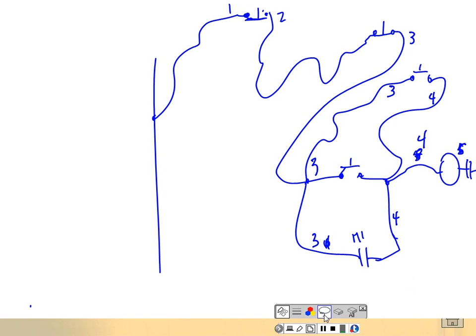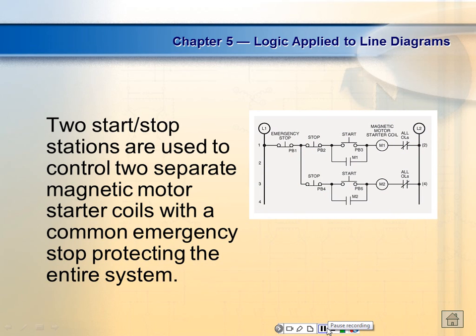2 minutes. Okay, so as we move along, these diagrams get more complex. Here we have an e-stop button. By the way, e-stop buttons normally do not remove power from the control circuit. It removes the power from the loads. So remember that. One of the qualifications for e-stop buttons is that we draw them as normally closed, but they're actually latching push buttons. Which means what? You have to twist them and pull out on them to get them to come off.